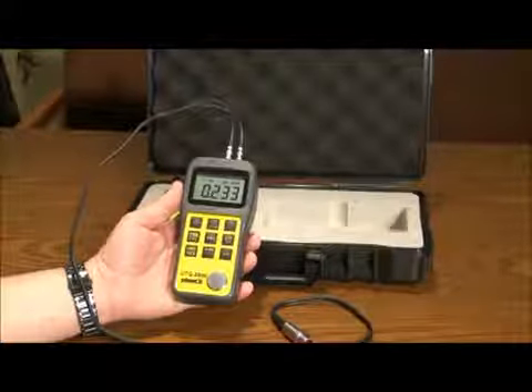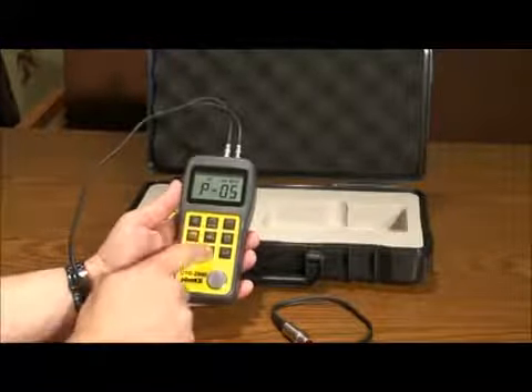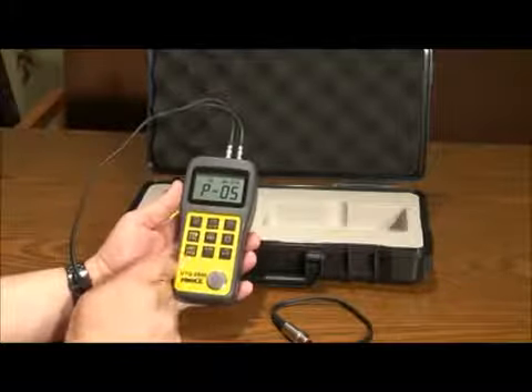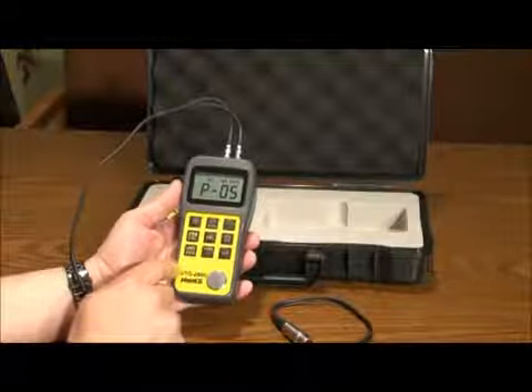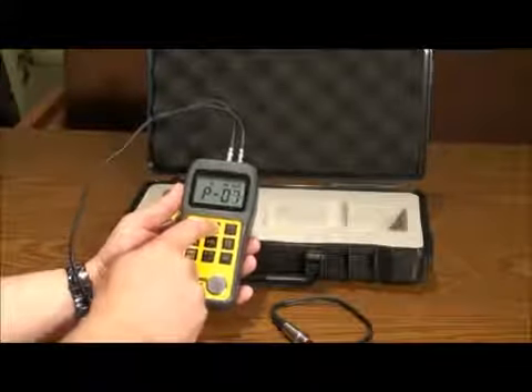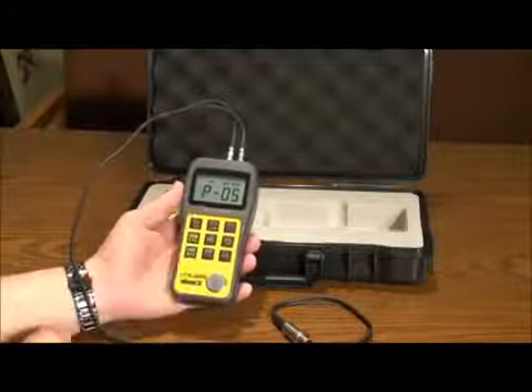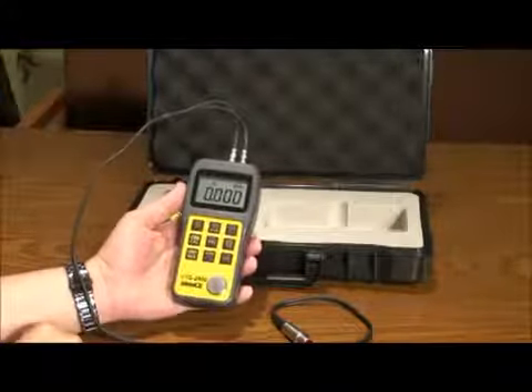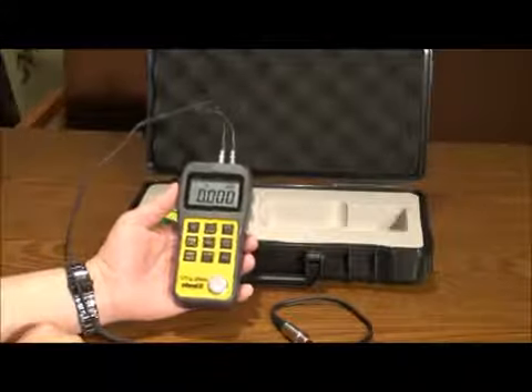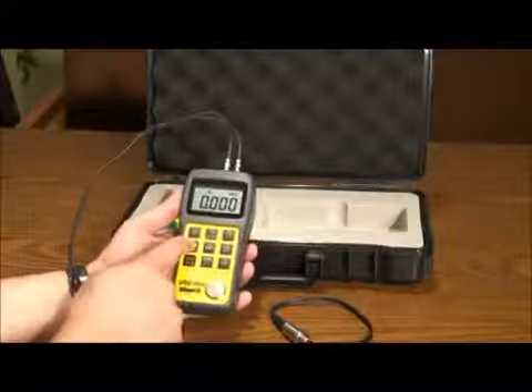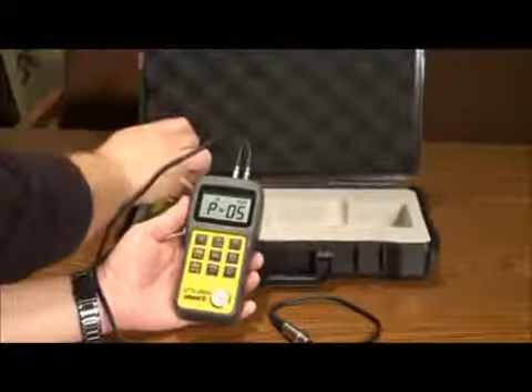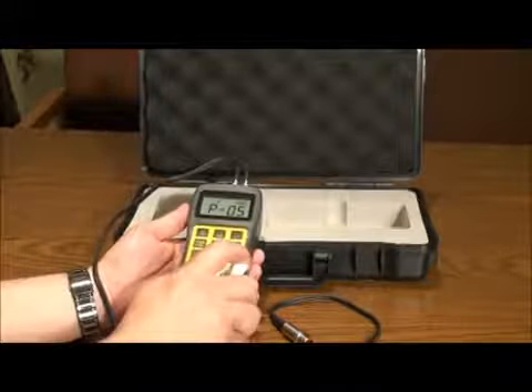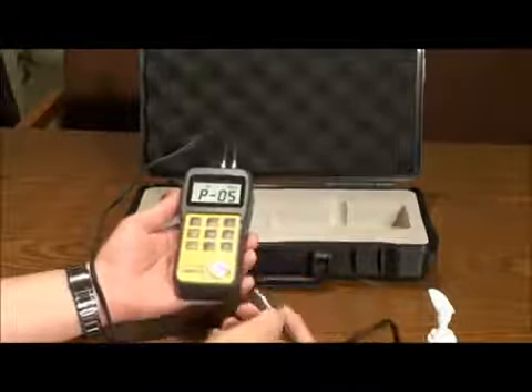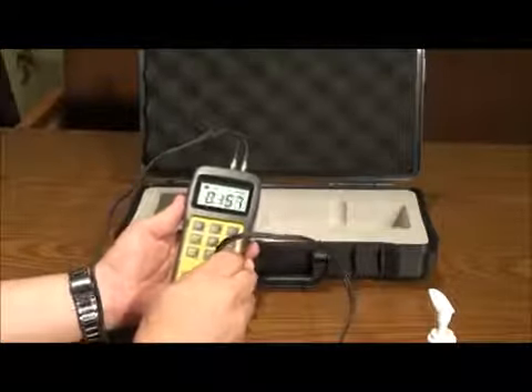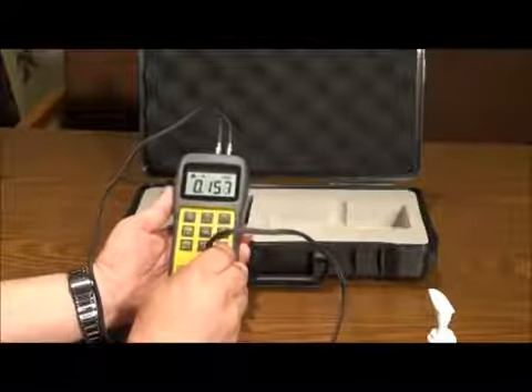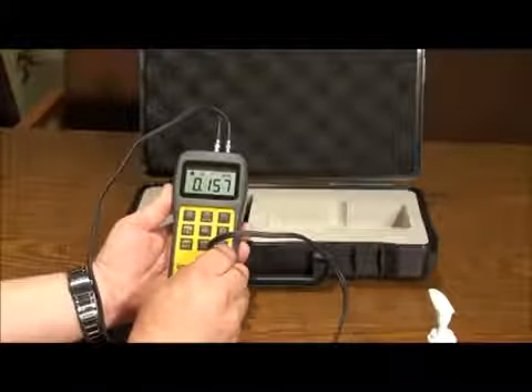Pressing the probe calibration key will allow you to change the probe setting in the menu. The unit is set to default on the general purpose probe included with the gauge. Scroll through the menu using the up and down arrow keys. Press enter to choose your selection and return to the home screen. In order to calibrate, after pressing the probe calibration key, apply gel to the test piece on the face of the unit. Press the probe flat on the test piece. Contact is shown on the screen and the unit will calibrate to 0.157 inches or 4 millimeters automatically.